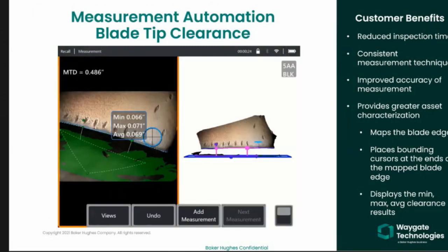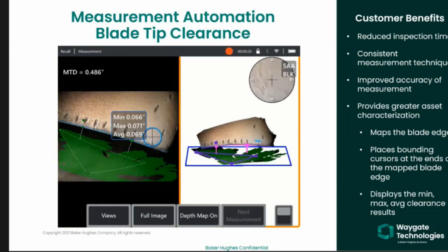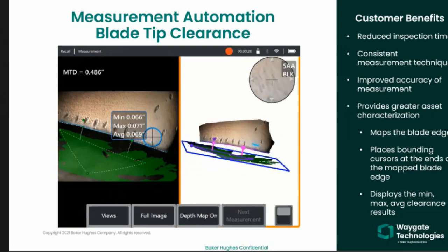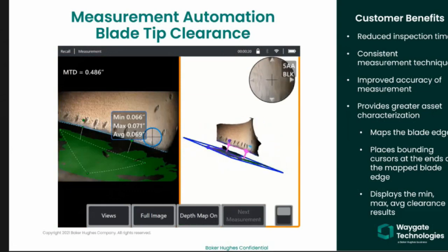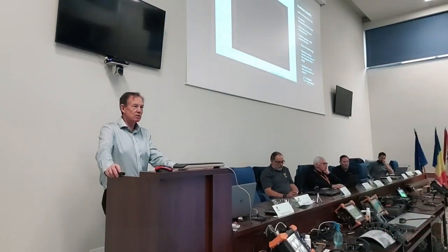So then we can go into different views of the same measurement you've just done. This is your 3D image capture that you've physically done, so you can have a very good representation of the actual measurement you took, so you know it's accurate. The problem in the past was that we did not know exactly where you were putting your cursors on your 2D image to see if that was accurate. With a 3D image, you don't make any mistakes.